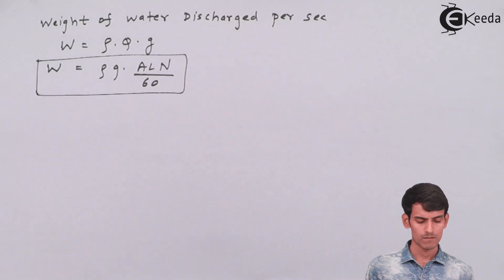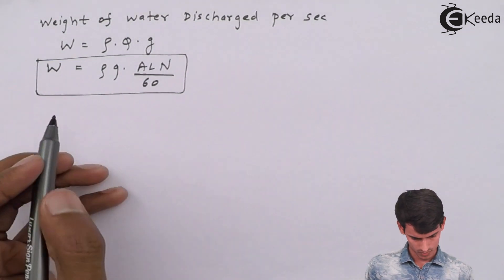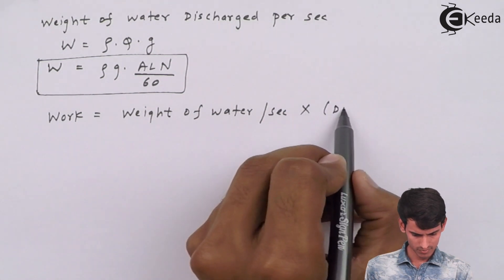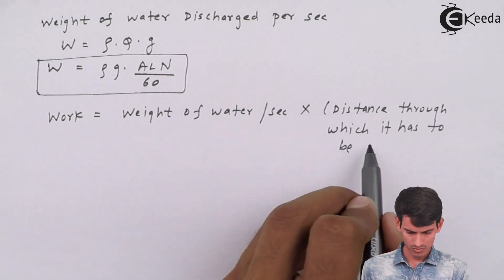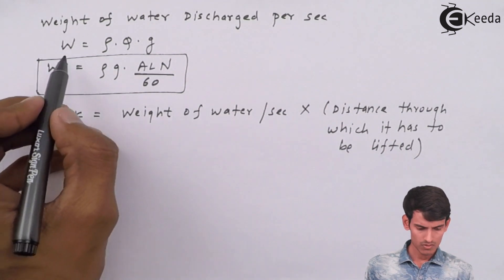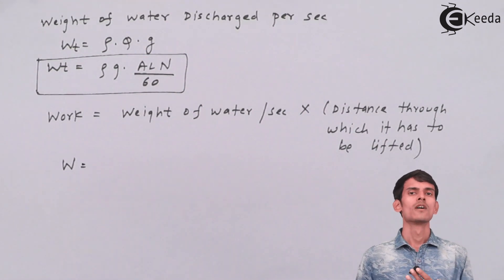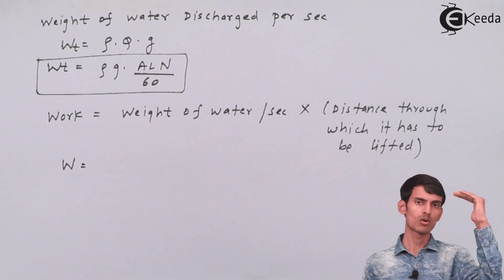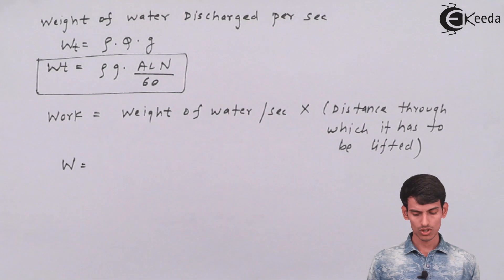Now you have to calculate the work done — it's very simple: weight of water discharged per second into the distance through which it has to be moved. The distance through which it has to be lifted is hs plus hd, where hs is the distance from the reservoir to the center of the pump, and hd is from the center of the pump to the outlet of the delivery pipe.